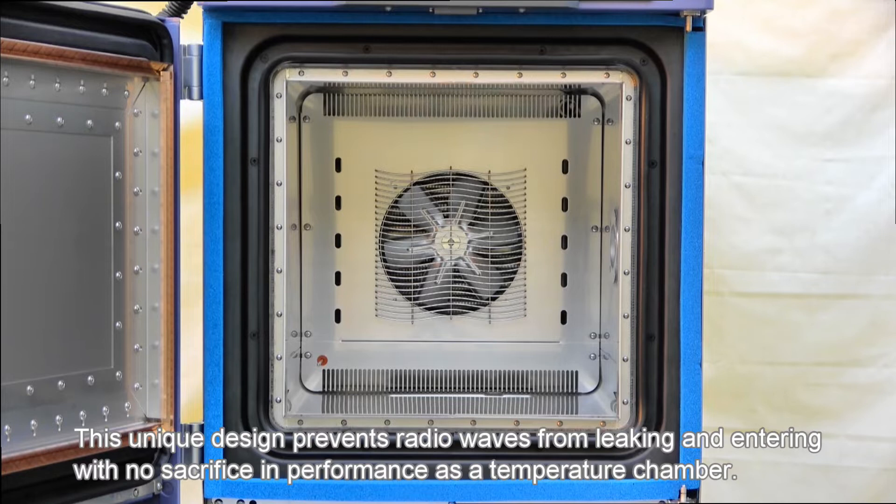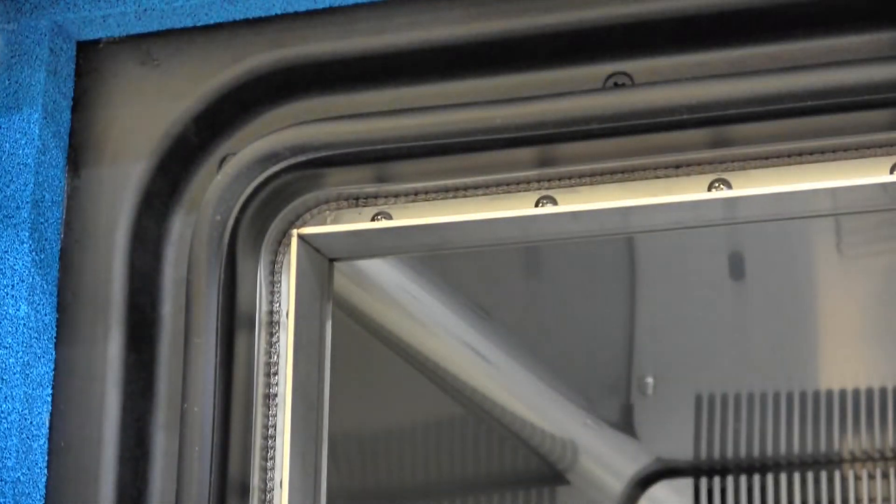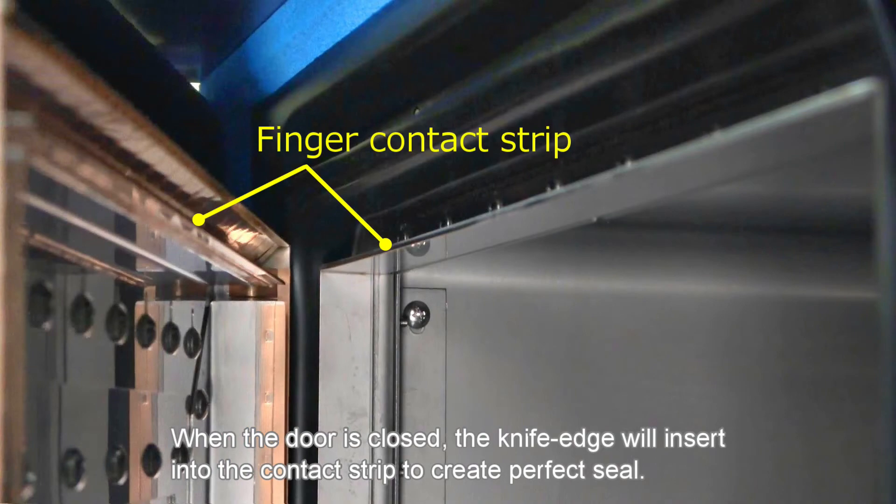This unique design prevents radio waves from leaking and entering with no sacrifice in performance as a temperature chamber. When the door is closed, the knife edge will insert into the contact strip to create a perfect seal.